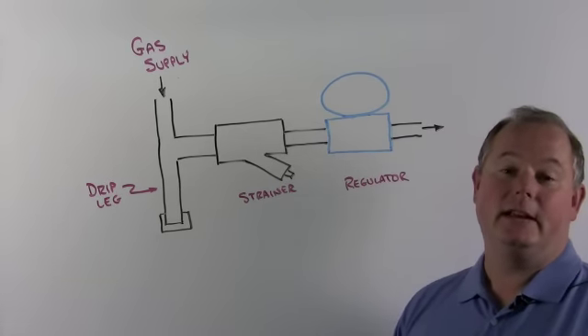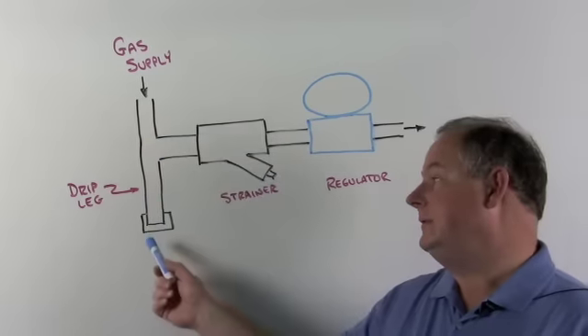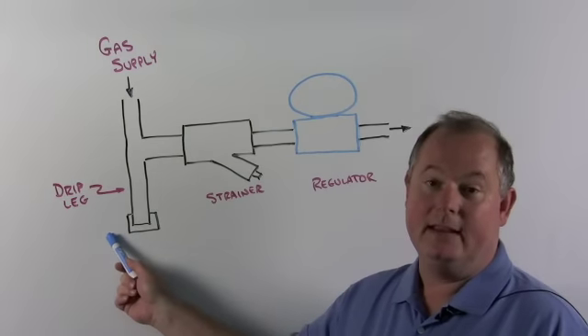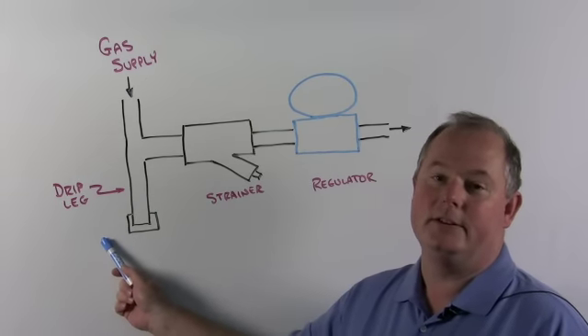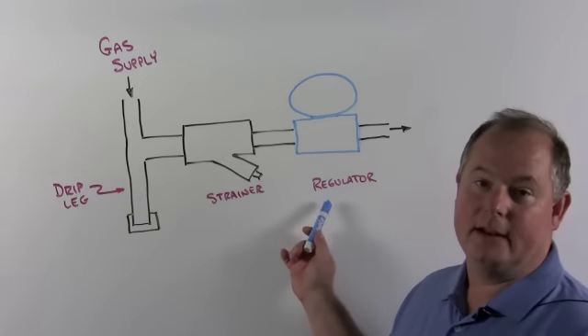Here's the normal setup of a gas regulator in a gas train. We've got the gas supply coming in. We always want to put a drip leg. It's easy to forget. It's kind of hard to do. You need the drip leg. You need the Y strainer, and then into the gas regulator.